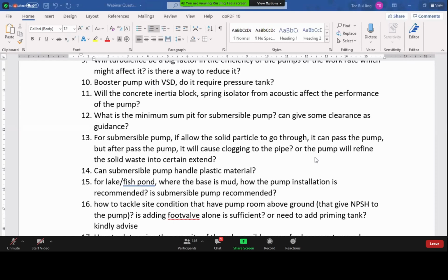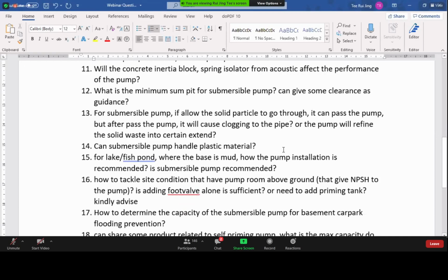Now, unless you talk about cutter or grinder pumps, you know, just now we showed you an example of a grinder impeller, where it cuts the waste that goes inside the pump. So if you have this type of pump or impeller, then it will actually cut off all the particles. But a normal pump cannot refine the solid waste. Yeah, the impeller does not do that. It basically just allows the particles to go through the pump to prevent clogging.